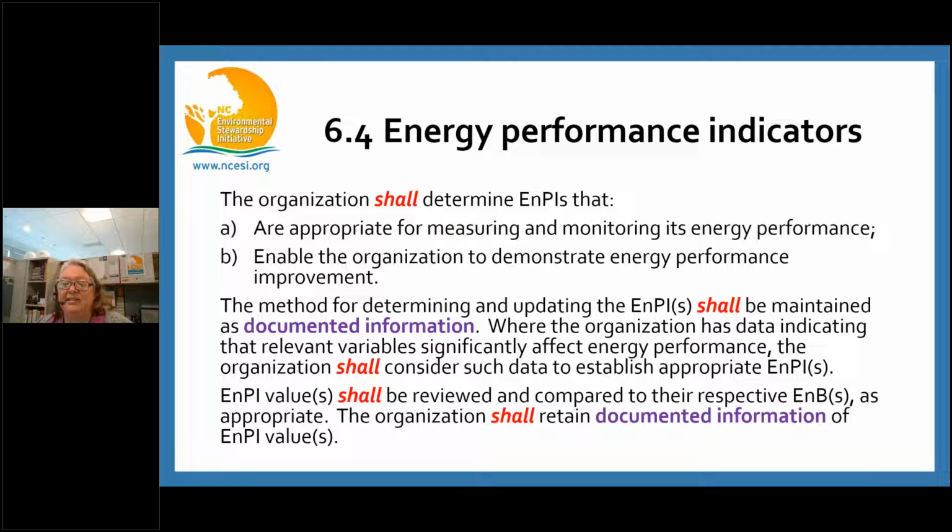So what are the EnPIs? They are the performance indicators. They're a measure or unit of energy performance as defined by your organization. So you might use something like kilowatt hours per square foot for a building, or total million BTUs per pound of steam for a large central boiler. You might use total kilowatt hours per ton for a chiller.